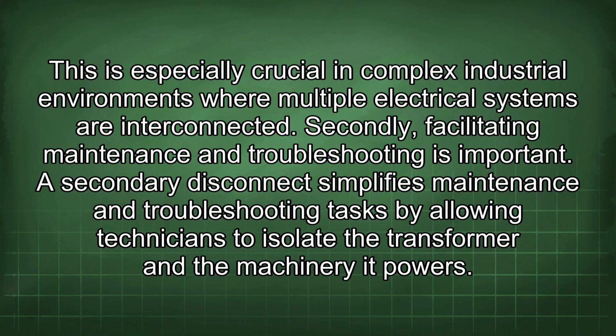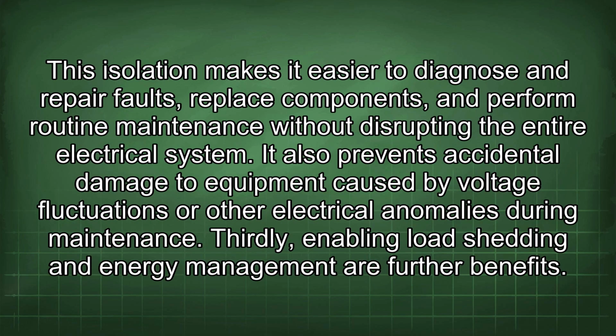Secondly, facilitating maintenance and troubleshooting is important. A secondary disconnect simplifies maintenance and troubleshooting tasks by allowing technicians to isolate the transformer and the machinery it powers. This isolation makes it easier to diagnose and repair faults, replace components, and perform routine maintenance without disrupting the entire electrical system. It also prevents accidental damage to equipment caused by voltage fluctuations or other electrical anomalies during maintenance.